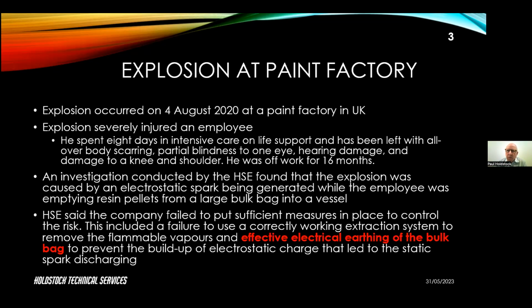The HSE said that the company had failed to put sufficient measures in place to control the risk, and that included a failure to control the flammable vapors through a correct extraction system, but also failure to use effective electrical earthing of the bulk bag. And this led to the buildup of electrostatic charge, which in turn led to the spark discharge. And it's that aspect, this failure to earth the bag, that really got my attention, because earthing is one of the fundamental controls that we have to control electrostatic risks. So that is what led me to believe that there perhaps was some requirement to raise the awareness of the standard and what the standards actually say.